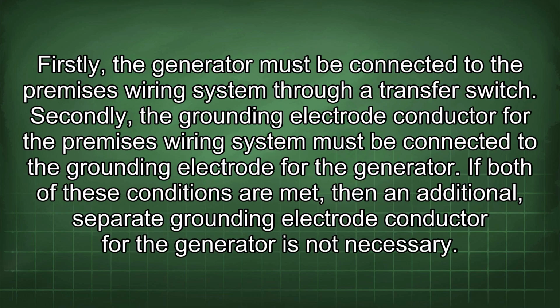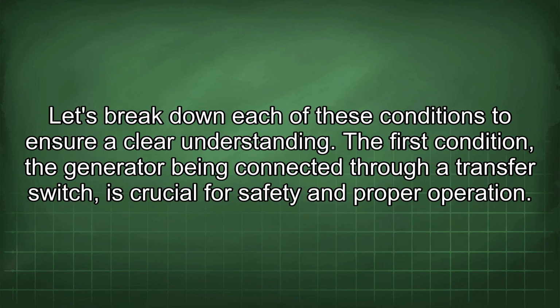Firstly, the generator must be connected to the premises wiring system through a transfer switch. Secondly, the grounding electrode conductor for the premises wiring system must be connected to the grounding electrode for the generator. If both of these conditions are met, then an additional, separate grounding electrode conductor for the generator is not necessary. Let's break down each of these conditions to ensure a clear understanding.